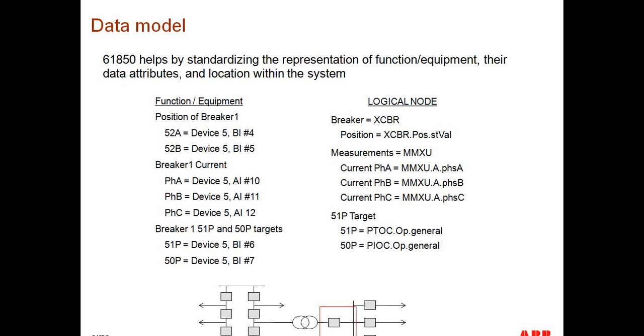In IEC 61850, the information is presented with a naming convention that's directly tied to the application. For example, logical information. In this particular case, we see this breaker, this incoming into this single bus substation. In the case of DNP, this could be seen in the spreadsheet as device 5, binary input 4 for the A contact of that breaker, and device 5, binary input 5 for the B contact. The way this information is presented in 61850 is we define a logical node, which in this case is XCBR, the representation of a circuit breaker, then .Pos, or position, and .stVal, which is the status value.